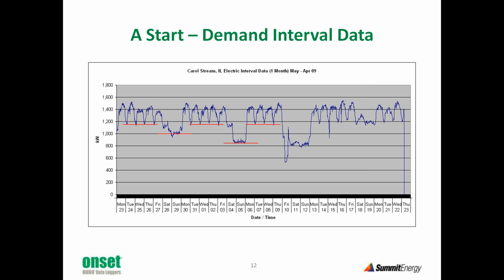Here is more of what we call demand interval data, just wiggly lines. It shows the load in a facility for an entire month. What it shows is the daily peaks and also the minimums at night, and it doesn't go down that much. But one thing you want to look at here is consistency. Does it go down to about the same level in the evening, or is there a lot of variation? And does it go down a different amount on the weekend than it does during the week? Now, this type of data doesn't give you many answers. It just provides the questions.